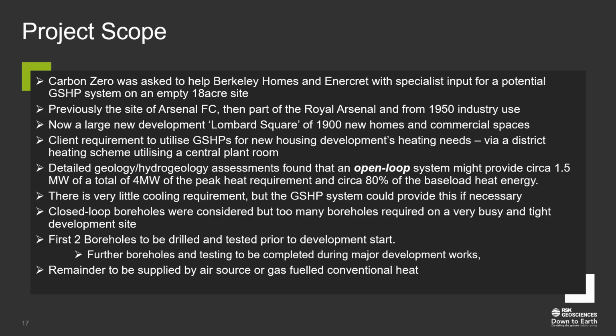Our hydrogeology assessment concluded that the ground beneath the site was very well suited for an open loop system. We recommended that the first two boreholes of the system be drilled and tested, so that using those results we could model how many more boreholes might be required to meet 80% of the base load heat energy they wanted from ground source.